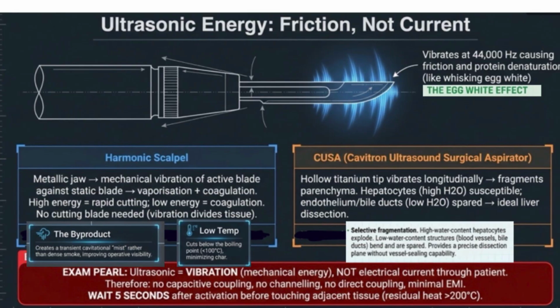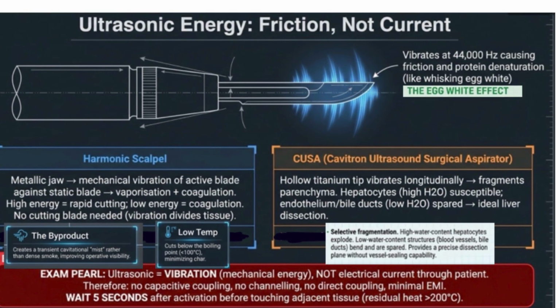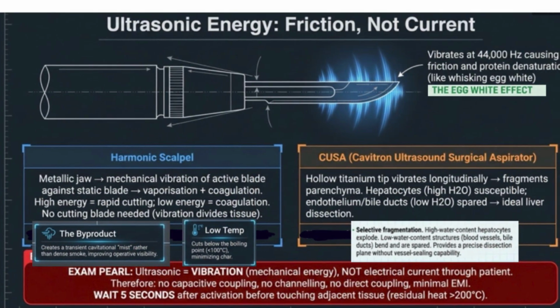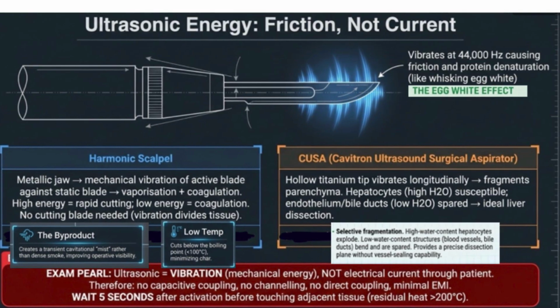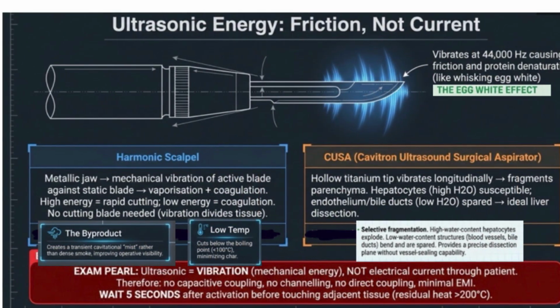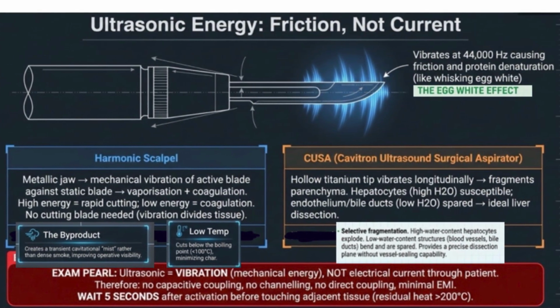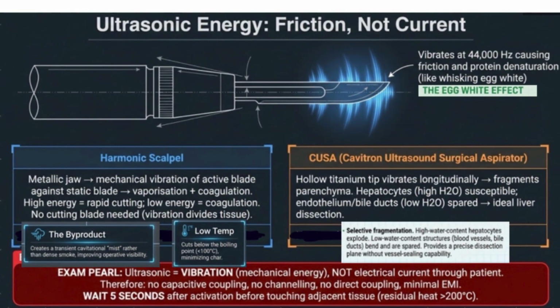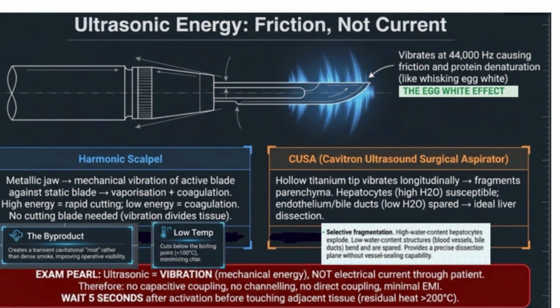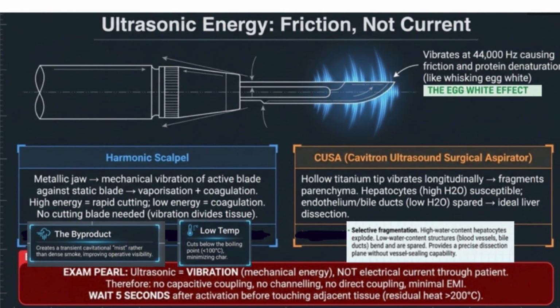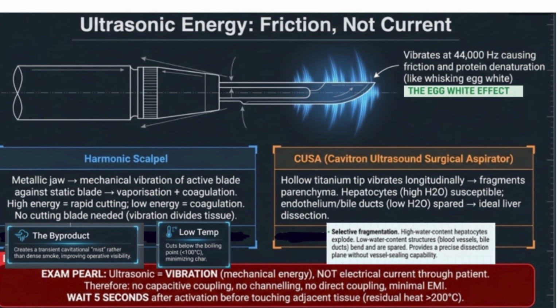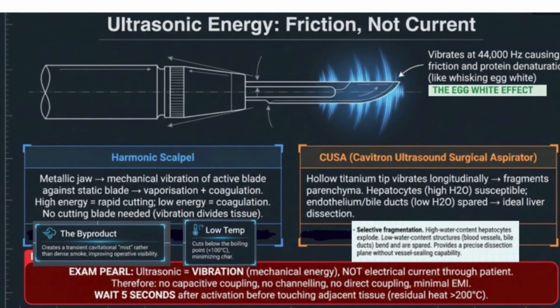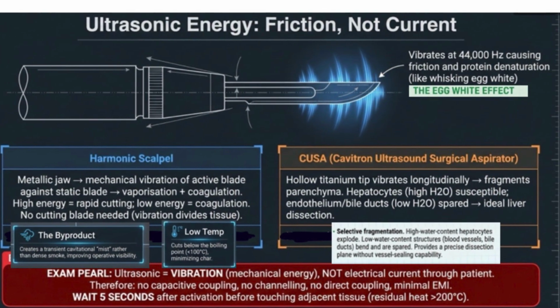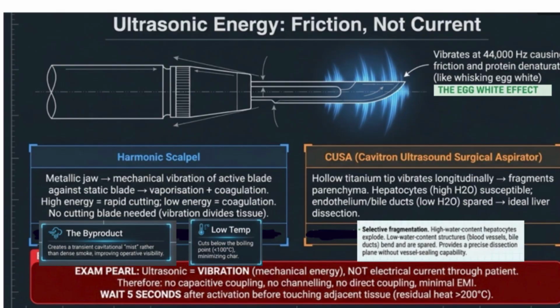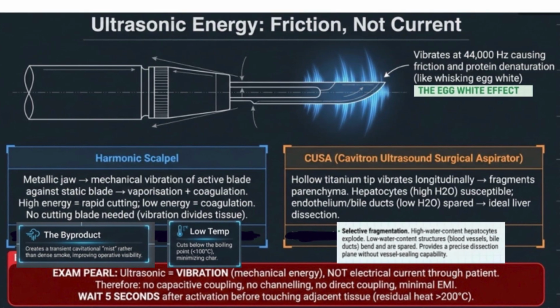Ultrasonics produce the egg white effect, that is, vibrations of 44,000 Hz cause friction and protein denaturation, which is like whisking of the egg white. The harmonic scalpel has a metallic jaw, with mechanical vibration of the active blade against the static blade, which causes the vaporization and coagulation. The high energy causes the rapid cutting, the low energy produces coagulation. No cutting blade is needed. The vibration divides the tissues.